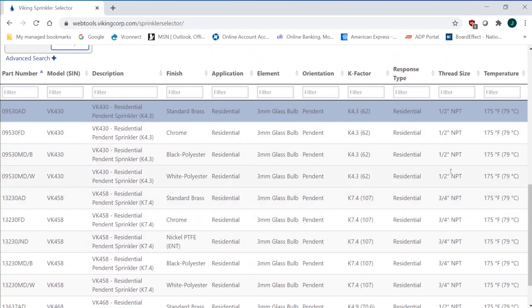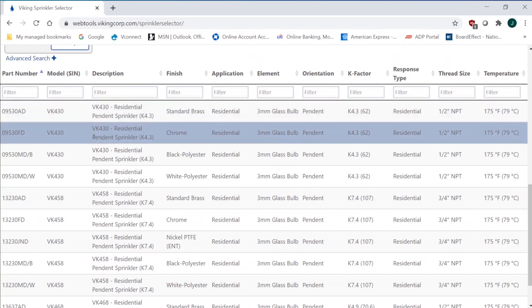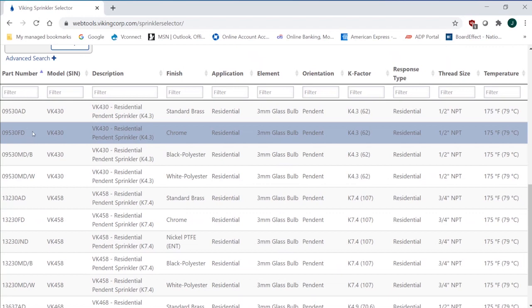You can see the thread sizes over here, the different K-factors that are available. But let's just say this was the sprinkler that I was looking for was the VK430. This one's chrome, residential, 3-millimeter glass pendant, K-factor of 4.3, half-inch thread, 175-degree. That's the one that I was looking for, so I get the part number as well.